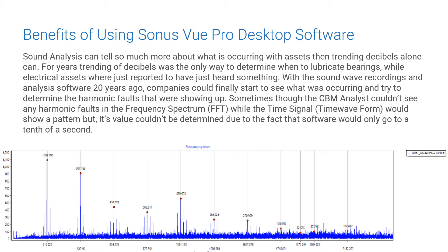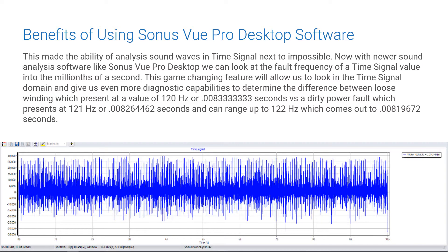Sometimes the CBM analysts couldn't see any harmonic faults in the frequency spectrum (the FFT), while the time signal or time waveform would show a pattern, but its values couldn't be determined because the software wouldn't go out to tenths of a thousandth of a second. Now, with newer sound wave analysis software like the Sonus Vue Pro Desktop, we can look at the fault frequency of a time signal value to the millionth of a second.